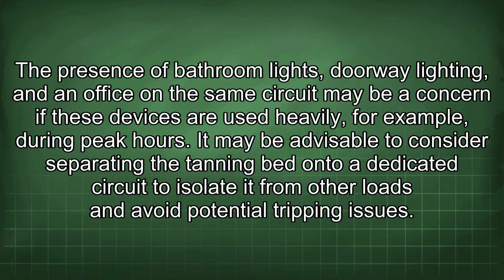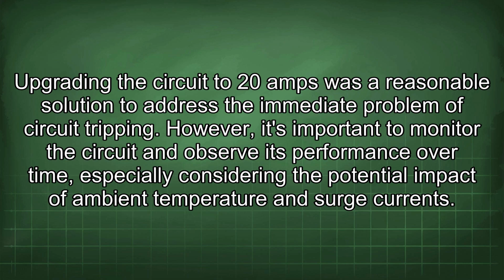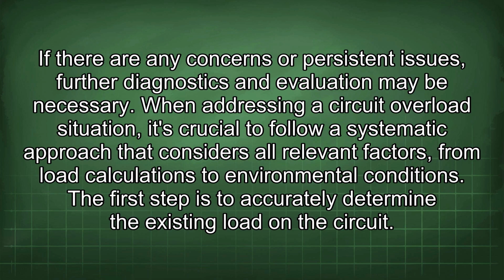The presence of bathroom lights, doorway lighting, and an office in the same circuit may be a concern if these devices are used heavily, for example, during peak hours. It may be advisable to consider separating the tanning bed onto a dedicated circuit to isolate it from other loads and avoid potential tripping issues. Upgrading the circuit to 20 amps was a reasonable solution to address the immediate problem of circuit tripping. However, it's important to monitor the circuit and observe its performance over time, especially considering the potential impact of ambient temperature and surge currents. If there are any concerns or persistent issues, further diagnostics and evaluation may be necessary.